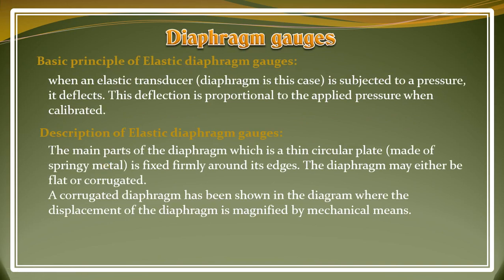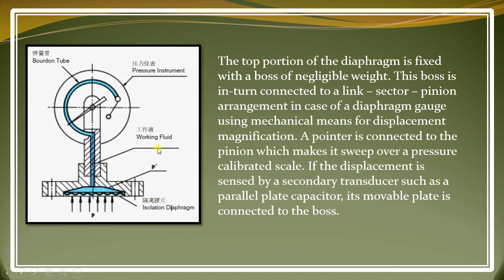Now let's talk about a diaphragm gauge. How can we make a diaphragm sensor into a diaphragm gauge? As we can understand, the sensors, such as Bourdon tubes and diaphragms, are the starting point, and every sensor can make a gauge. That's why we are using it. With the diaphragm, we fix its corners and apply a pressure, and the output will be exerted. We can make a mechanical assembly with pinion and link sector, and all these parts, and we can rotate the pointer also. If we want an electrical output, we can use the diaphragm to make a capacitor, and when the diaphragm deflects, the capacitance will change, and we can get an electrical output also. We can also get a resistive or inductive type output from this.